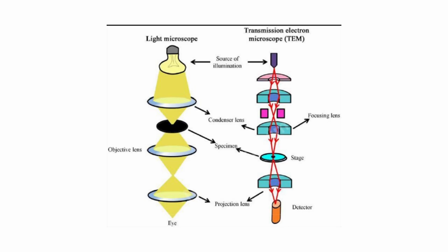So all the statements are correct. Here you see the electron beam. If there are any gas particles, instead of going through the lenses, it can actually diffract outwards. The diffracted electron beams will also reach the detector, but those beams are not interacting with your specimen, so they will give background noise.